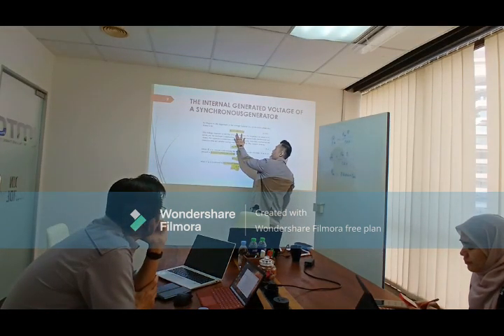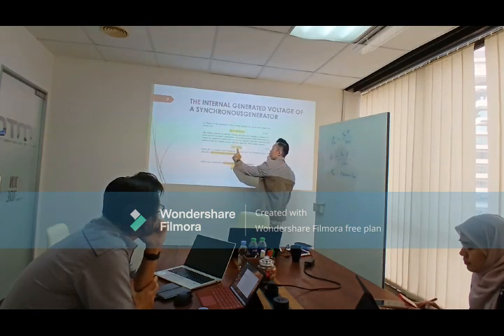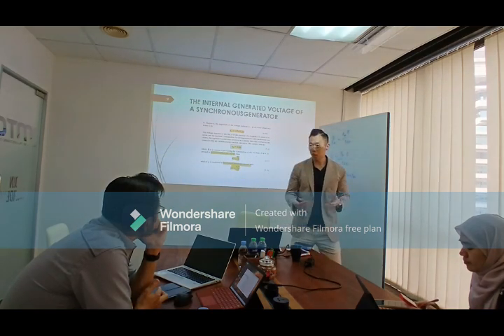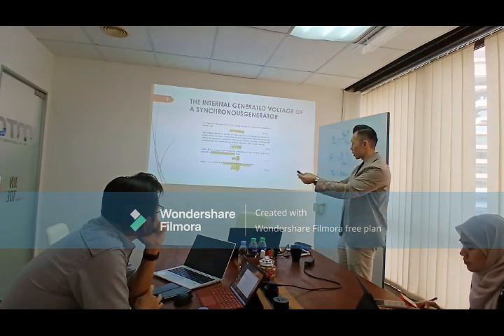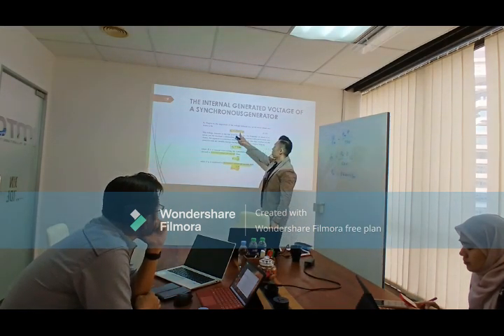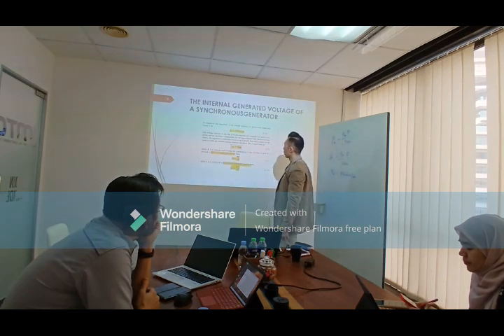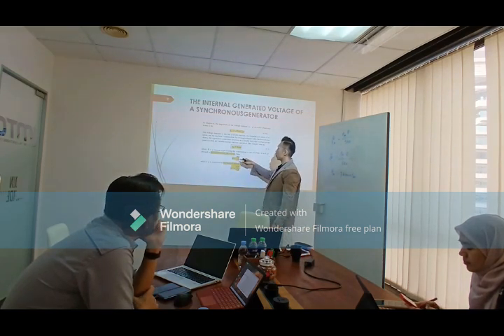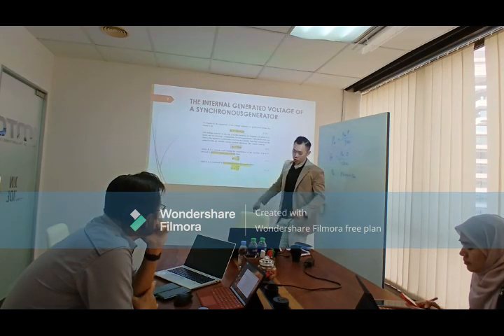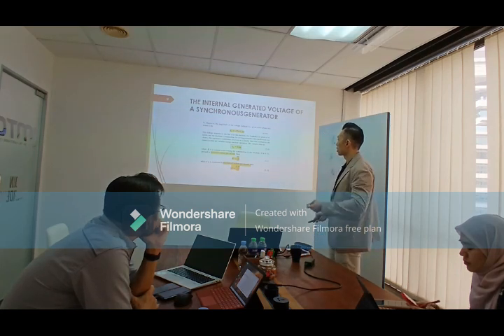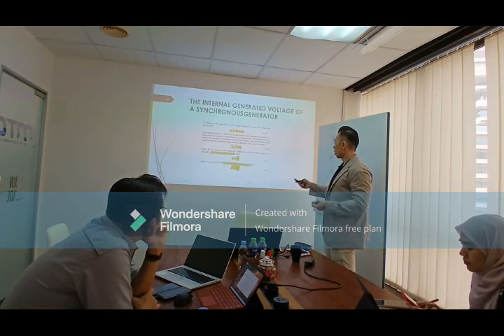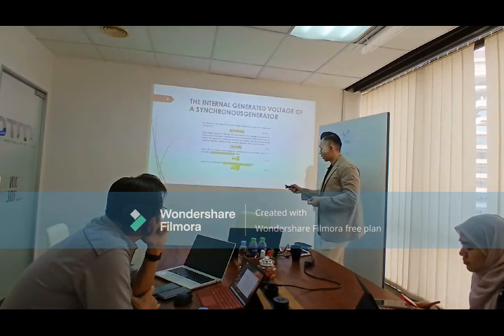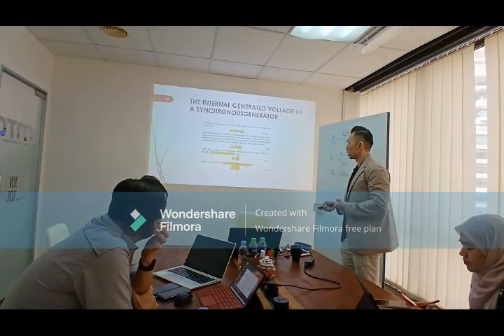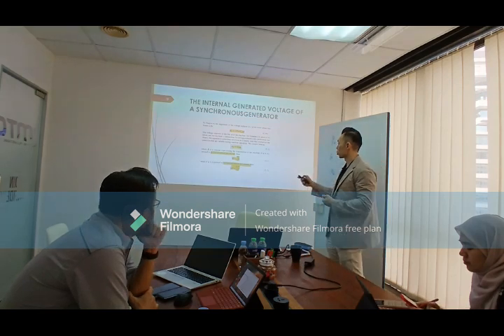If you examine this equation, there are several constants here - these three terms are constant, so I can ignore them and call it constant K. This constant K is typically provided by the manufacturer - it's a constant that stays with the generator forever, since it comes from the number of turns multiplied by two other constants. What we need to concern ourselves with is only the flux and the omega, which is the turning frequency. There are two ways to determine K, but this is the manufacturing constant, just provided here for information.